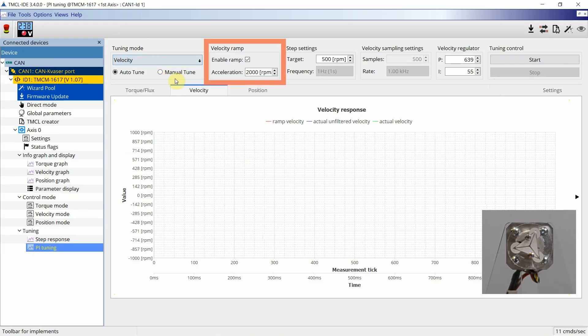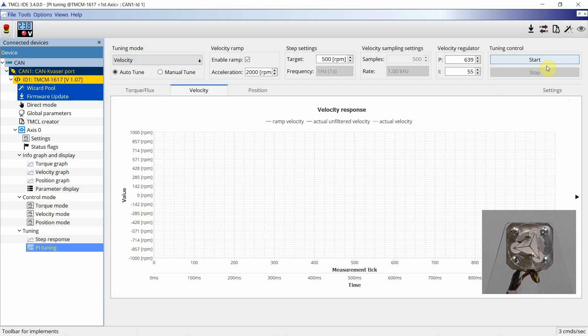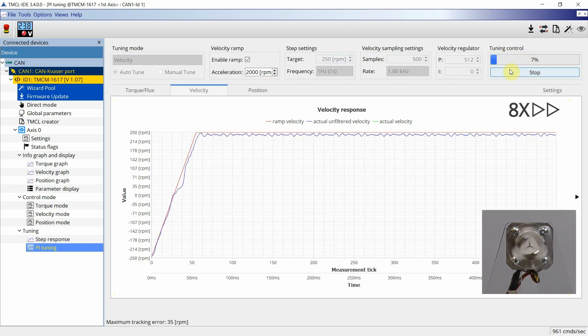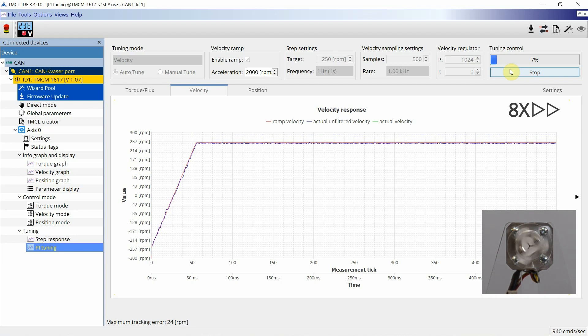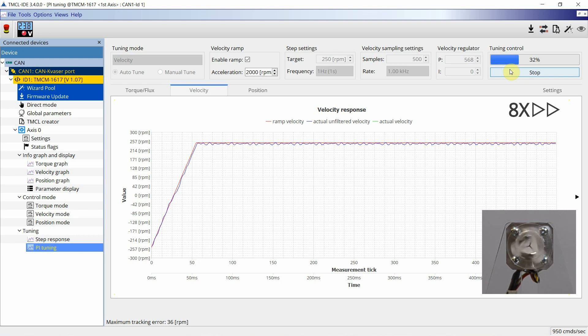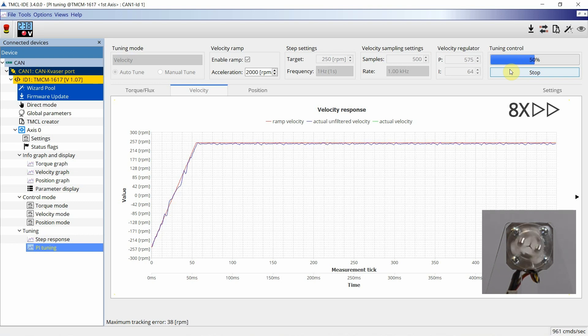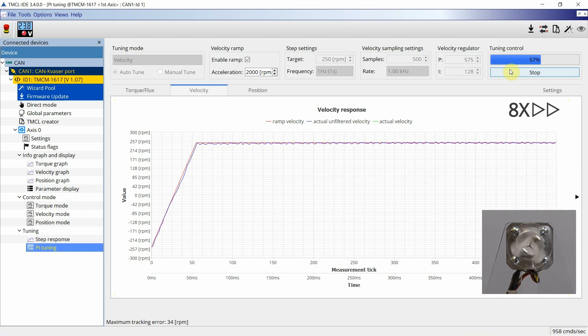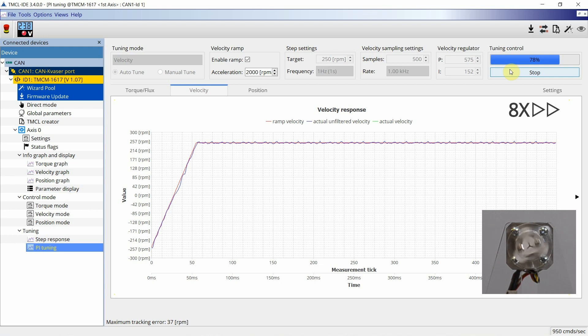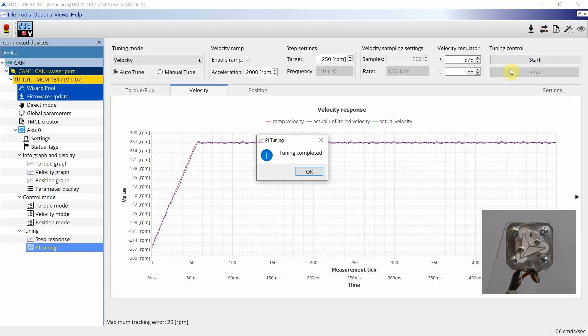In the velocity ramp settings, the velocity ramp can be enabled and the acceleration can be set according to the application or left at default. Then, set the target velocity the motor will be tuned to. The signal generator will generate target step responses from the motor while constantly checking against the PI parameter. First, the P and then the I parameter will be tuned. After the error has been minimized, the auto-tuning is complete.